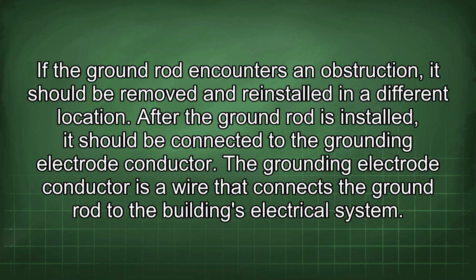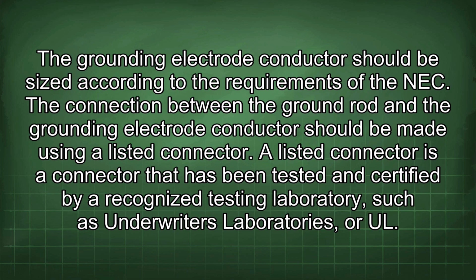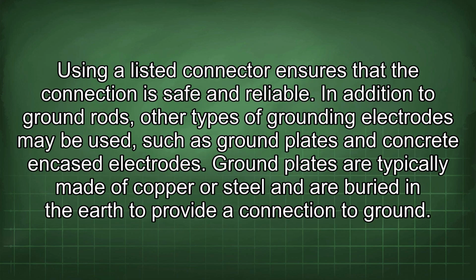After the ground rod is installed, it should be connected to the grounding electrode conductor. The grounding electrode conductor is a wire that connects the ground rod to the building's electrical system. The grounding electrode conductor should be sized according to the requirements of the NEC. The connection between the ground rod and the grounding electrode conductor should be made using a listed connector. A listed connector is a connector that has been tested and certified by a recognized testing laboratory, such as Underwriters Laboratories or UL. Using a listed connector ensures that the connection is safe and reliable.